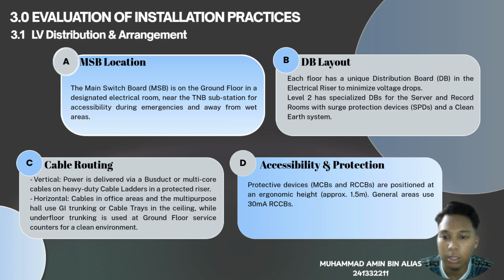And the last one is accessibility and protection. Protective devices like MCB and RCCB are positioned at an ergonomic height, approximately 1.5 meter. And for the general areas, we use 30 milliamp for RCCB.